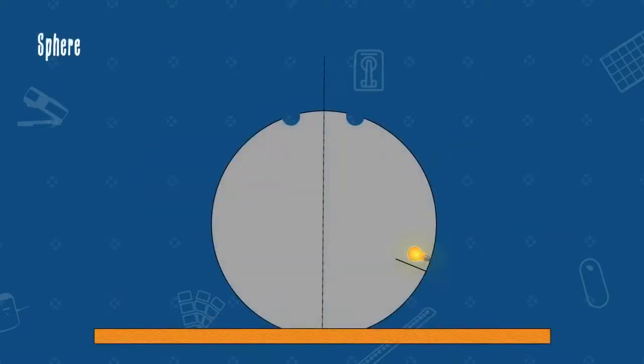Next are spherical instruments, which capture light reflected from all angles of a sample. This measurement can include or exclude the surface appearance of your sample. These devices are commonly used for measuring color that has been applied to textured surfaces, such as textiles, carpets, and plastics, as well as glossy or mirror-like surfaces, including foil printing.